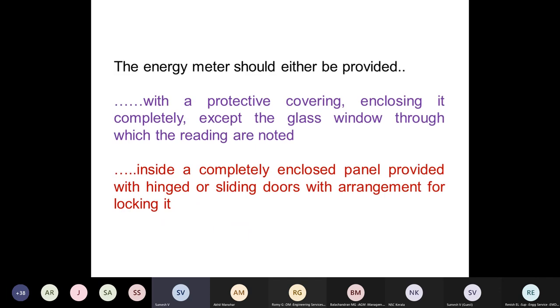That is, the energy meter should either be provided with a protective covering enclosing it completely, except the glass window through which the readings are noted, or be inside a completely enclosed panel provided with a hinged door or sliding door with the arrangement for locking it. Here it is stated that it should be installed inside a completely enclosed panel with the hinged door. It is not supposed to install the meter on the hinged door. The meter should be inside the box, but that box can have a hinged or sliding door to take the reading and other things. So the problem in the above accident was that the meter and the electrical equipment were installed on the hinged door. Because of that, each time the door is opened, the wire is pressed with the sharp edge of the panel, and the insulation is damaged.